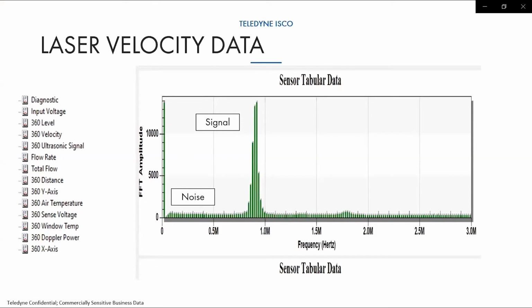If I still have a strong return signal, and my X and Y axis shows that it's still level, I don't necessarily need to send somebody out to the site to take a look at it. I can look at the air temperature to let me know my ultrasonic sensor is reading properly. And then we've got Doppler power, which is that return signal.